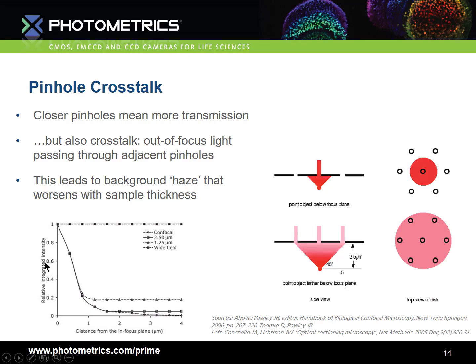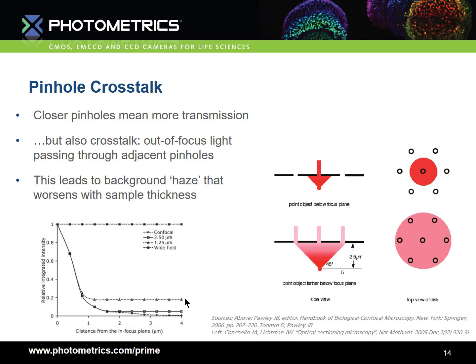To quantify this, here we have a plot of the relative intensity of light given off by a fluorophore versus the distance vertically from that fluorophore. For a wide-field image, where we have no optical sectioning ability whatsoever, there's no difference in the relative intensity as we get further vertically from the fluorophore. However, for a confocal laser scanning microscope, the optical sectioning is really quite good, and four micrometres from the sample, we'd expect no light whatsoever. For spinning disk confocal, with pinholes spaced far apart, we still have fairly good optical sectioning and fairly good blocking of out-of-focus light. However, as we decrease the distance between pinholes, our relative intensity is fairly high, meaning that we have strong background haze. The consequence is that if you expect to be examining fairly thick samples, you need to use a spinning disk with a large separation between pinholes.